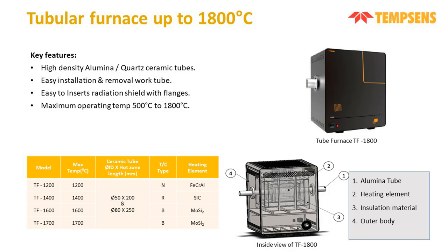Now we are coming to our next furnace, which is the tubular furnace, which goes to around 1800 degrees Celsius. The main feature of our tubular furnace is that we use a high density alumina and quartz ceramic tube, which provides us great uniformity and the ability to withstand high temperature without cracking. We have made the tube furnace for easy removal and installation of the work tube. The tube furnace is divided into four categories according to temperature, which are 1200, 1400, 1600, and 1700 degrees Celsius. The tube ID is around 50 and 80, and the length we can customize according to the customer requirement.